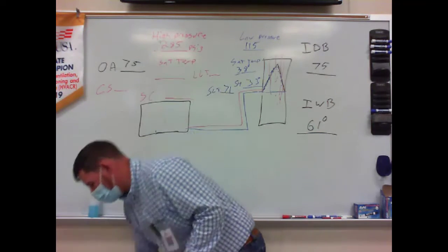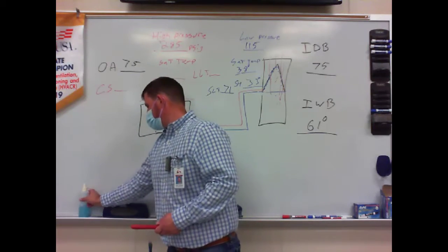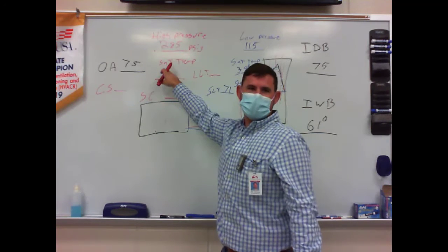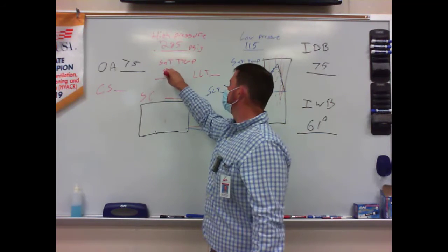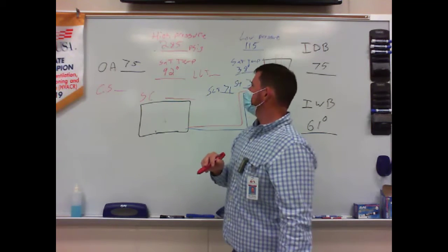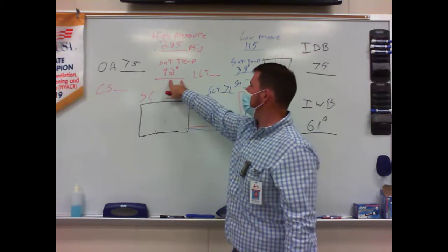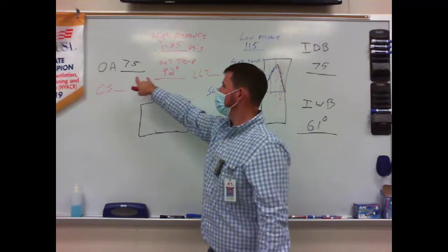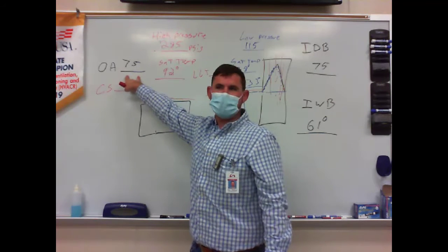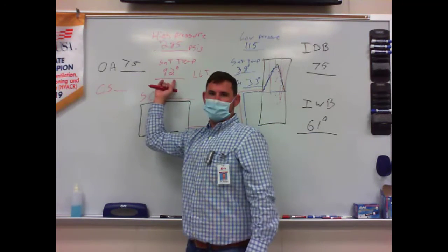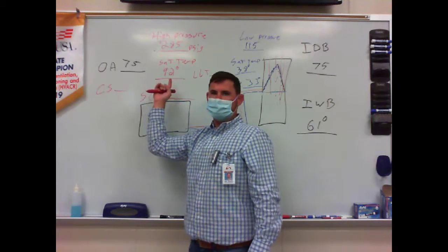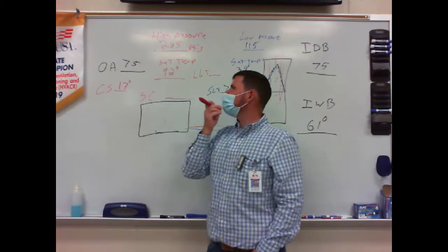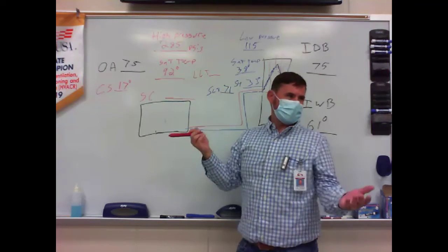So 285 psig. Saturates at what temperature? All right. So I'm at 92 degrees on my saturation. My space is 75 degrees. What's my condenser split? How much warmer am I? About 17 degrees. Is that good, bad?